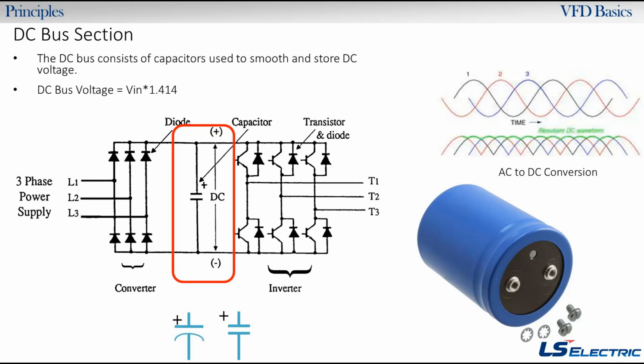So some of you, I'm sure, have called us before and asked about, oh, I got an overvoltage, oh, I got an OVT, I got an OUT. All the same thing. Most common trip you'll ever have on a VFD is OUT, and not just our VFDs. I've seen it on all kinds of VFDs, very common, and it's really tricky to figure out because it's all about this DC bus. If you ever jump up to like 800 volts from a voltage spike on the input or from some kind of regenerative feedback on the output, that's what will trip you out. So it's a little bit tricky to troubleshoot.